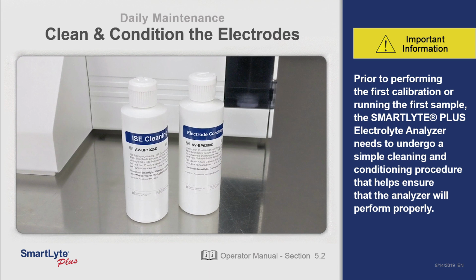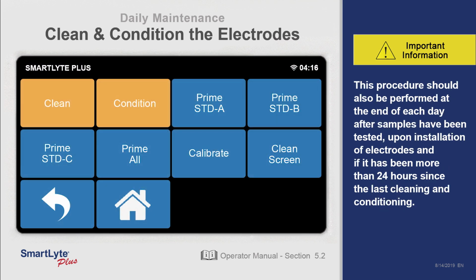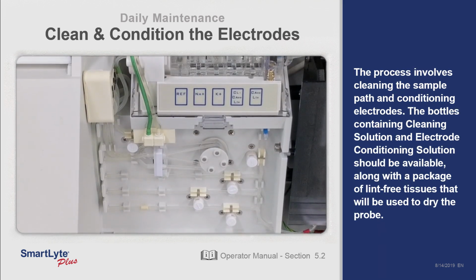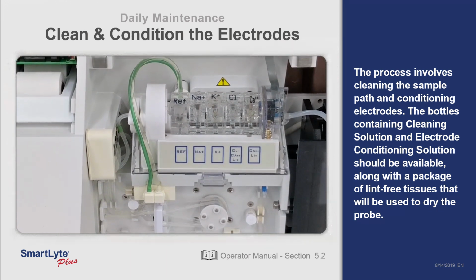Maintenance on the SmartLyte Plus. Prior to performing the first calibration or running the first sample, the SmartLyte Plus electrolyte analyzer needs to undergo a simple cleaning and conditioning procedure that helps ensure the analyzer will perform properly. This procedure should also be performed at the end of each day after samples have been tested, upon installation of electrodes, and if it's been more than 24 hours since the last cleaning and conditioning. The process involves cleaning the sample path and conditioning electrodes.